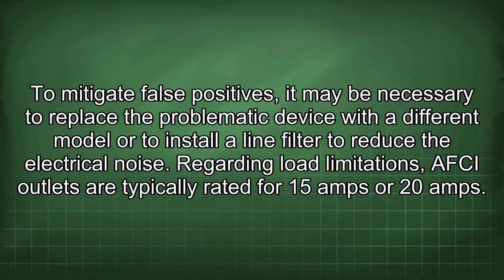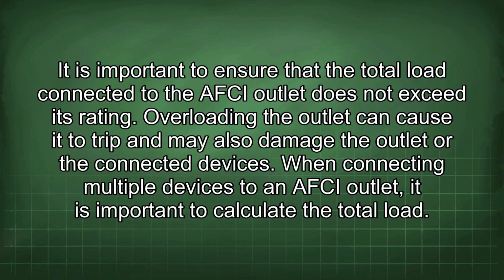To mitigate false positives, it may be necessary to replace the problematic device with a different model or to install a line filter to reduce the electrical noise. Regarding load limitations, AFCI outlets are typically rated for 15 amps or 20 amps. It is important to ensure that the total load connected to the AFCI outlet does not exceed its rating. Overloading the outlet can cause it to trip and may also damage the outlet or the connected devices.